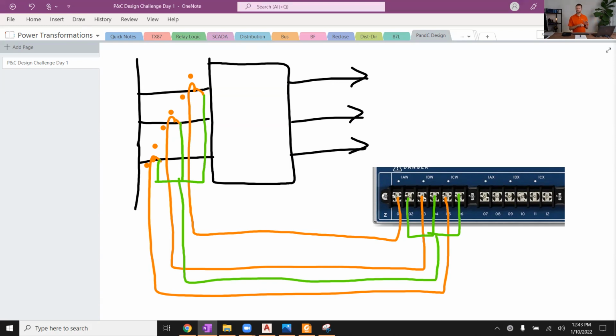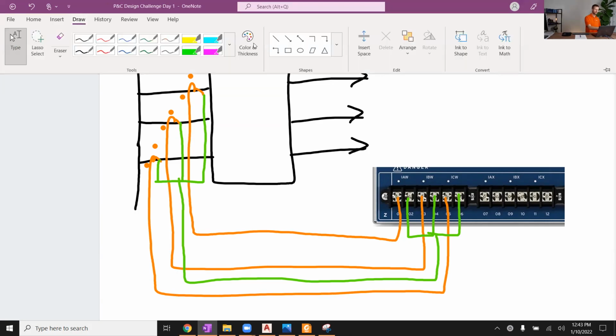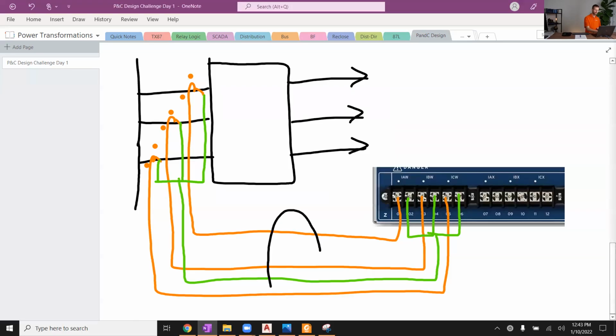So what am I showing you here? This is more like a 3-line rendition of the currents and the CT circuits. What I can help you understand here is that typically this is 1 cable. This might be like a 4-conductor number 10, or 10 American wire gauge, which is a pretty common wire size that we use for CT circuits in a substation environment. So all 4 of these wires, A, B, and C, and neutral, are bundled together in that common cable jacket. And that's how we would go about wiring these current inputs on the back.